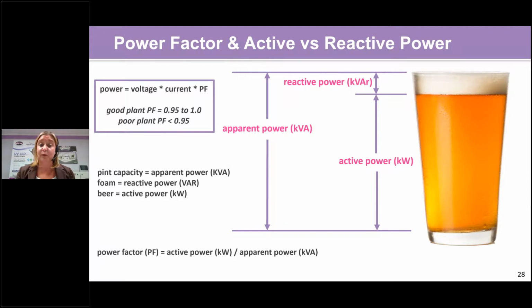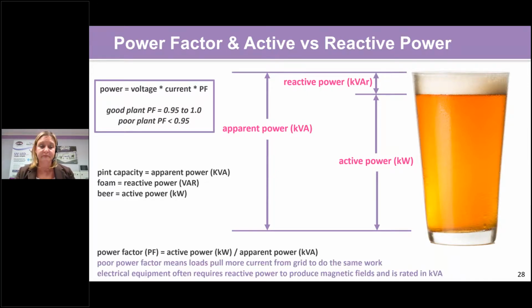If you don't do it, then the substation has to do it by adding capacitors to the line to balance the inductive loads in your plant. So poor power factor means that the load, your machines, pull more current from the grid to do the same work. And we often specify electrical equipment in that apparent power. We specify our UV curing systems, LED and arc, in terms of the kVA rating. And that is what you will see on our spec sheets and all of our documentation. So it's important to understand what that is.